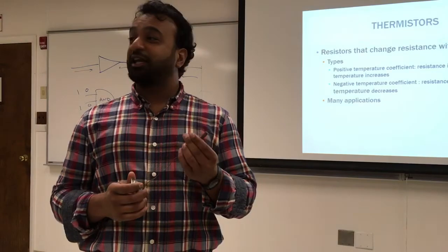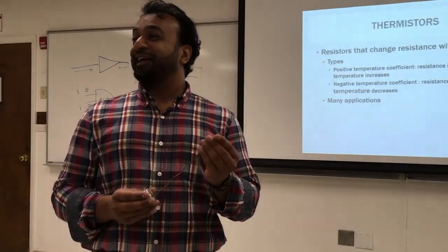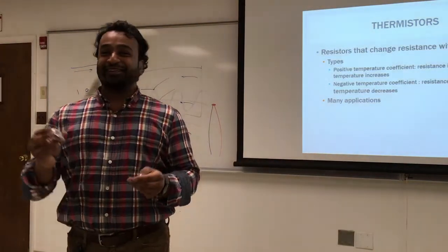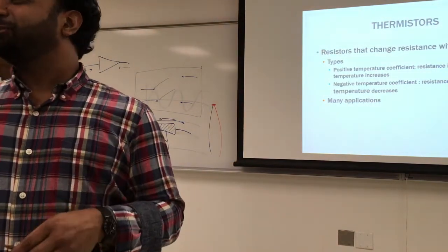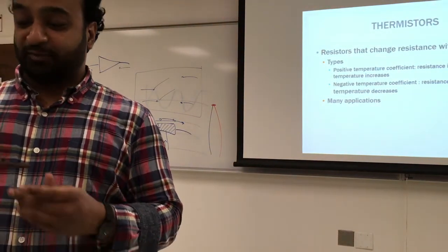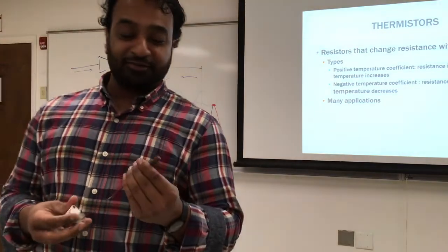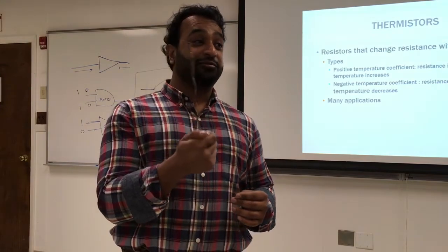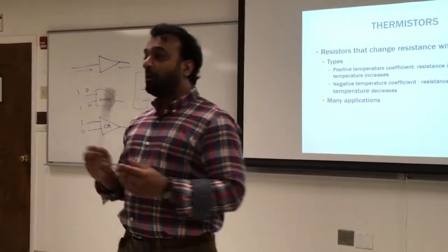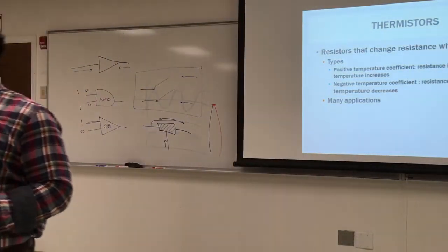Not purposely. It's experimentation, for the sake of science, to see what happened. So we overheated it, not purposefully. We thought it was stuck or malfunctioned, and it exploded, and it was kind of violent. So don't do that. Look, this is actually thick copper, so it takes a lot of pressure to burst this. So always know what the limits are for those probes.